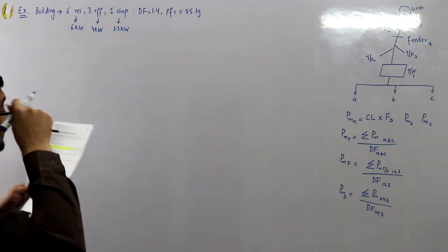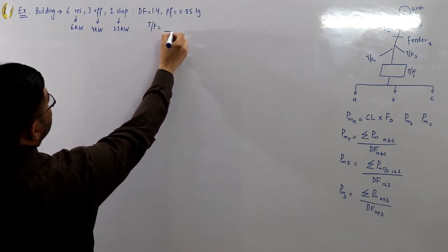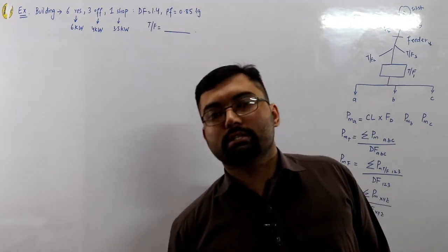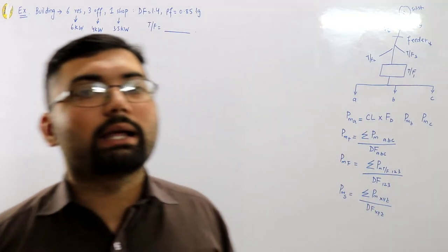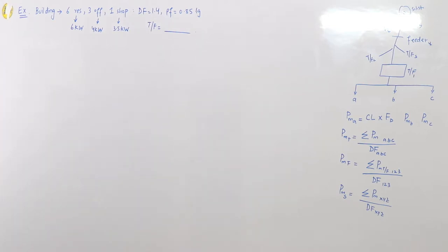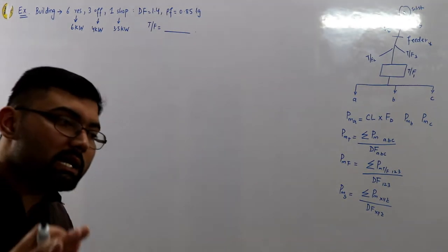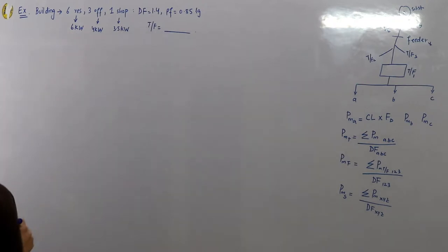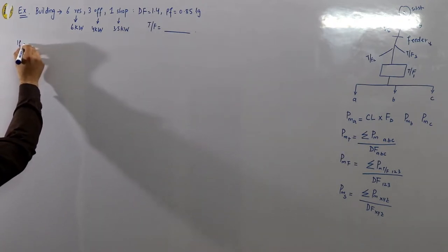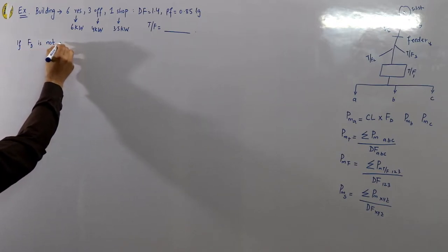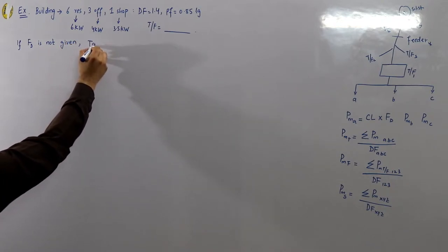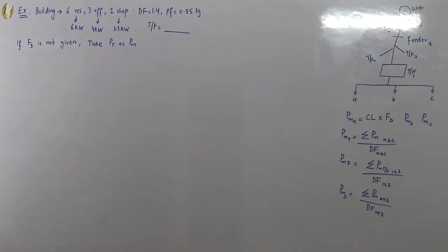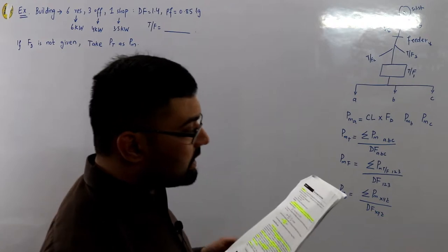Determine the rating of the transformer required. For the transformer requirement, we need to know the maximum demand. We are given the connected load. When the demand factor is not given or not mentioned, take the connected load equal to the maximum demand — that is, take PT as equal to PM.